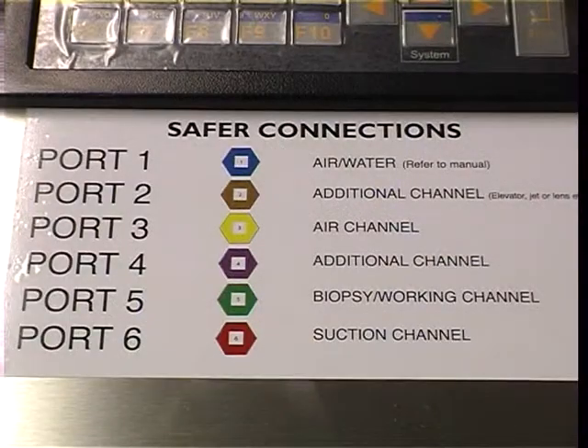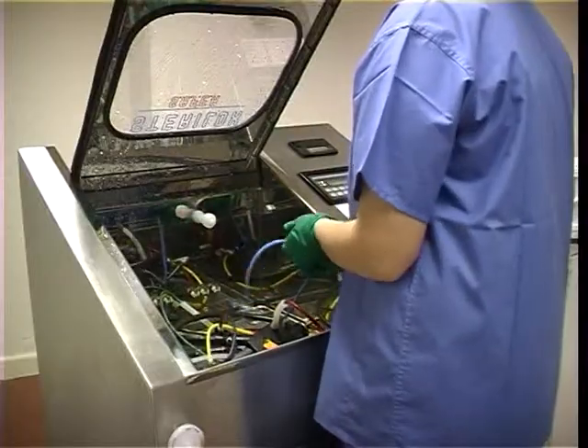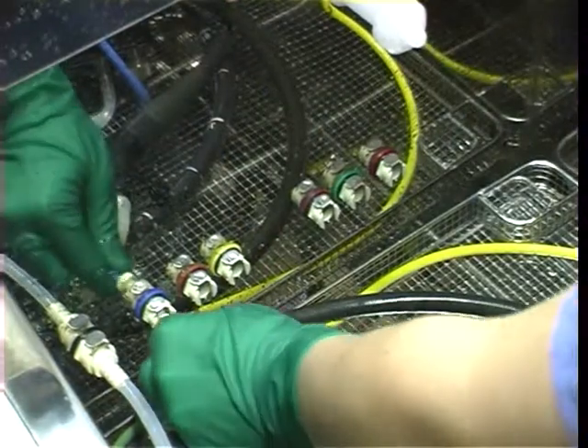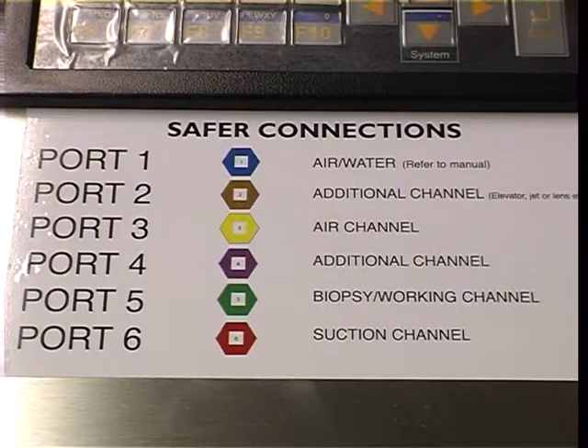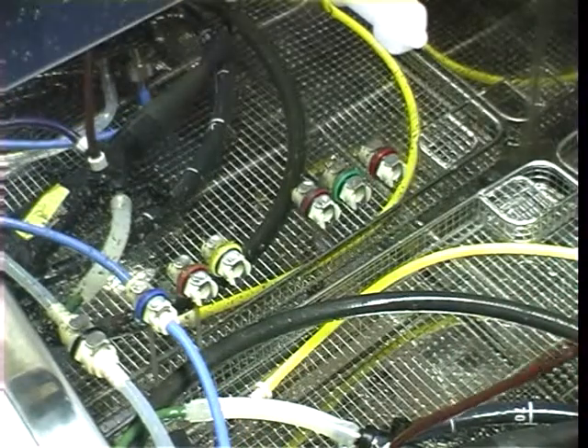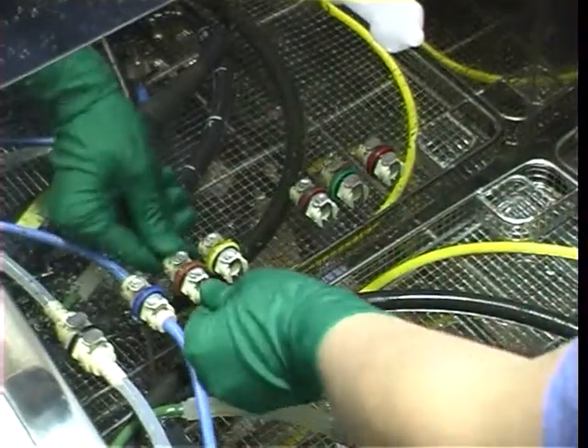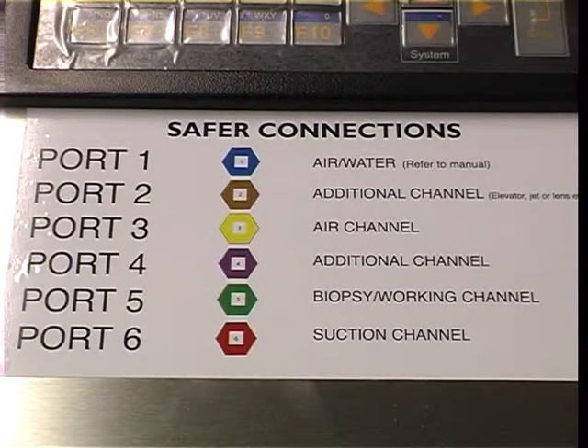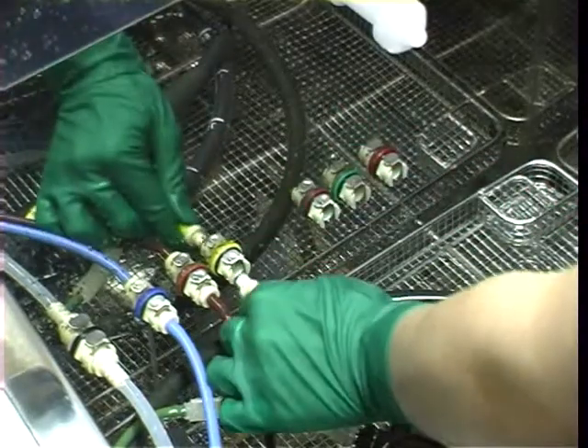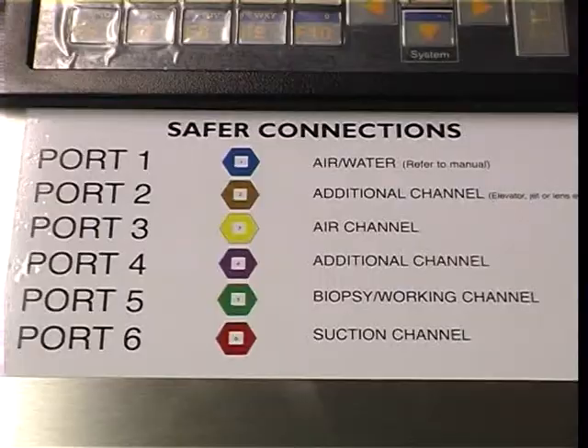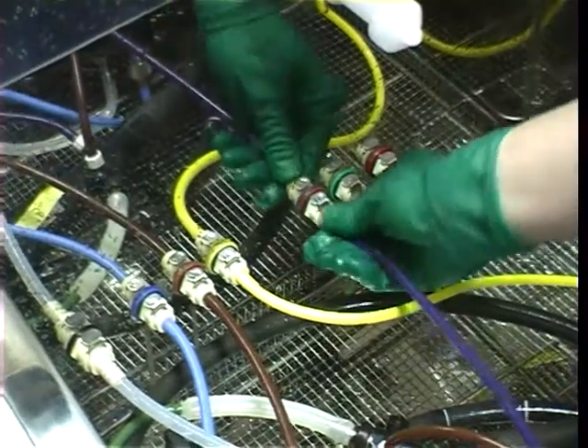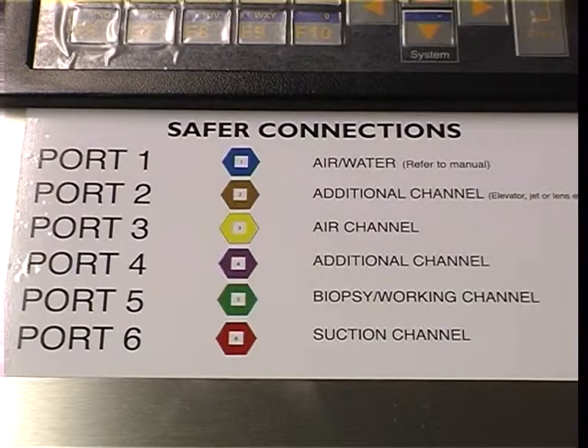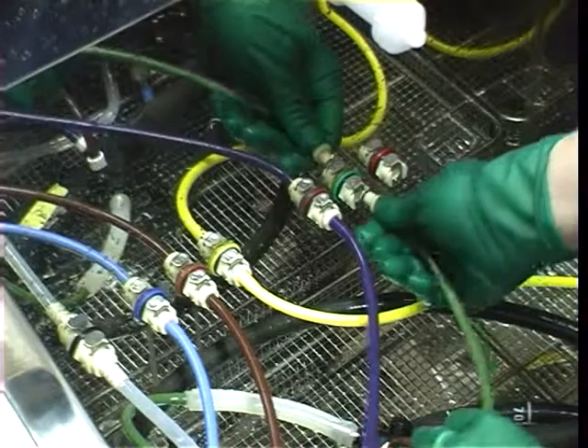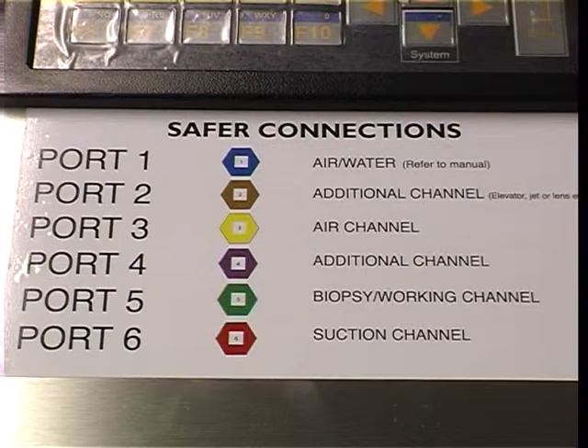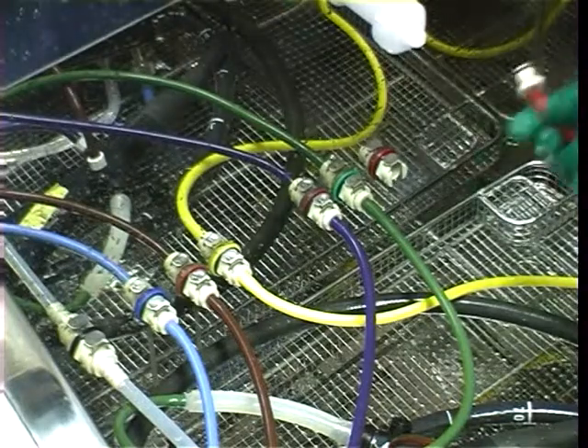The air-water channel should be connected to the blue bulkhead and connected with the blue tubing. When flowing any additional channel, for example an elevator, jet or lens channel, then the brown bulkhead and brown tubing should be used. If your air channel does need to be flowed, the yellow bulkhead and yellow tubing should be used. Any additional channel, for example an auxiliary water channel, should be connected to the purple bulkhead and purple tubing. The biopsy working channel should be connected using the green bulkhead and the green tubing. Your suction channel should be connected using the red bulkhead and the red tubing.